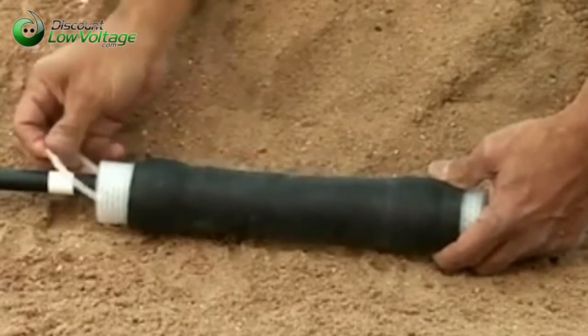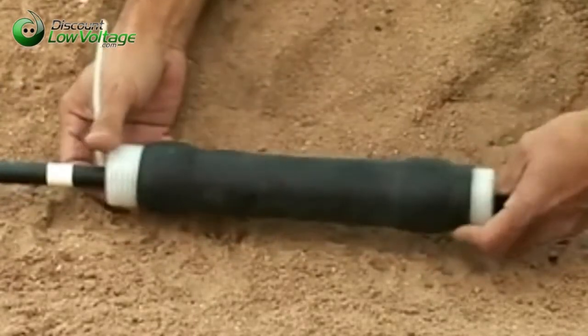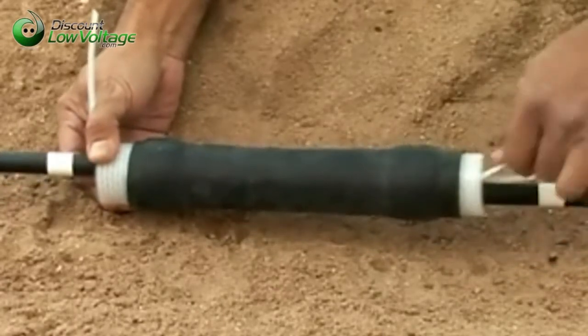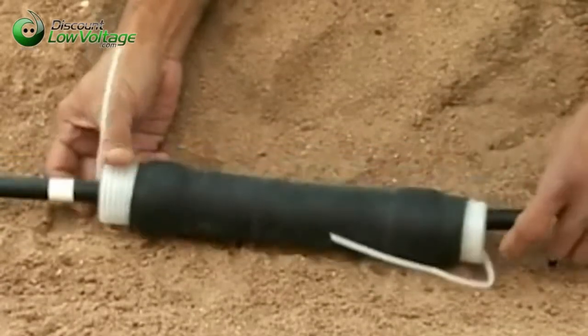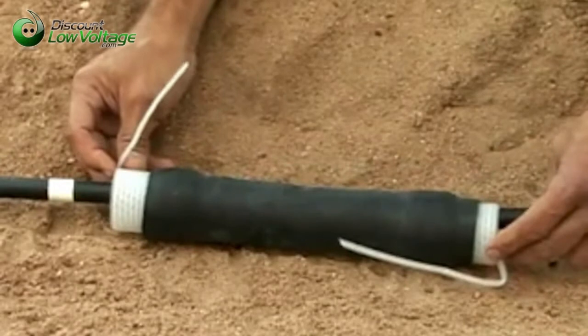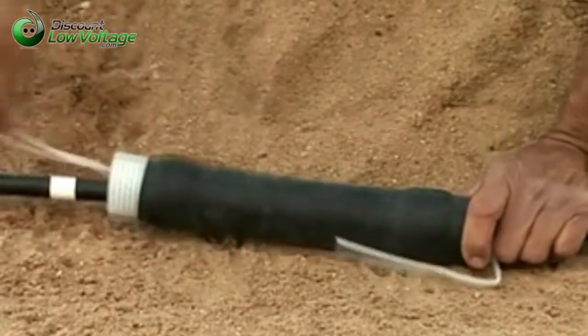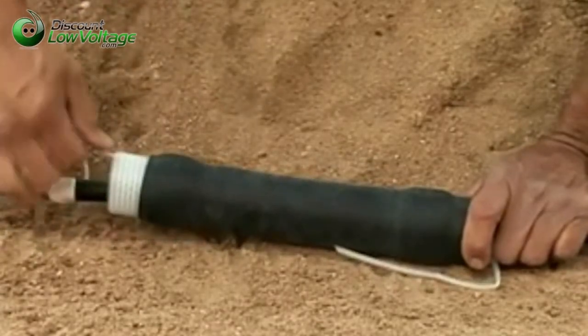The smaller size QSLV-M splice will accept cable sizes of 8 to 3-0 gauge, while the larger size will accept 2-gauge to 1,000 kcmil. It also can be used for dig-in repairs, sheath repairs, and insulation of transition connectors for inline conductors.